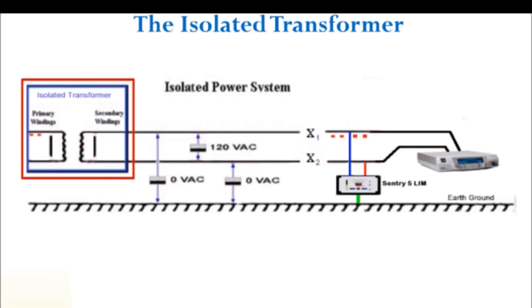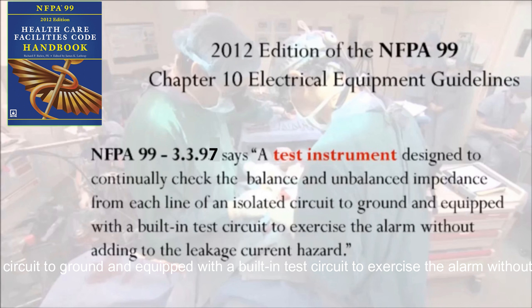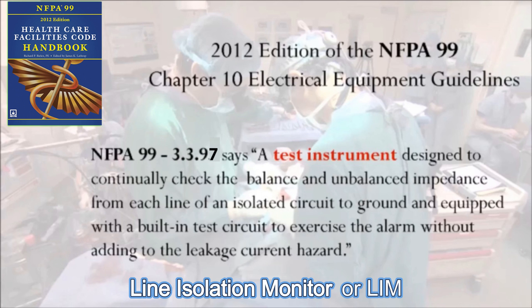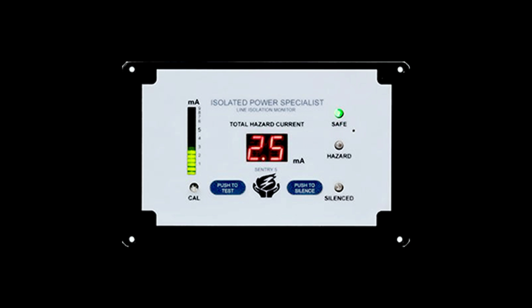Nor are the secondary windings referenced to earth ground. The second component is defined in NFPA 99 codebook section 3.3.97. It says: a test instrument designed to continually check the balance and unbalanced impedance from each line of the isolated circuit to ground, and equipped with a built-in test circuit to exercise the alarm without adding to the leakage current hazard. So we need a test instrument to let us know if any earth ground is starting to creep into the system. That test instrument is called a line isolation monitor, or LIM. Isolated Power Specialists markets a line isolation monitor called the Sentry 5.